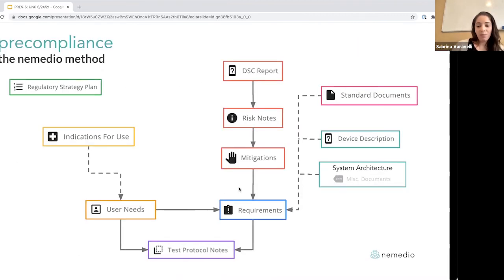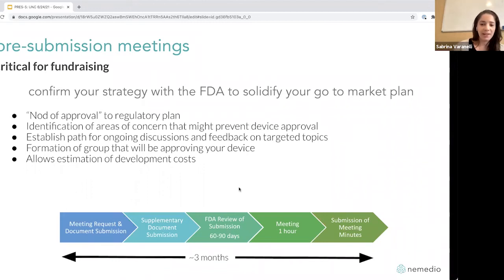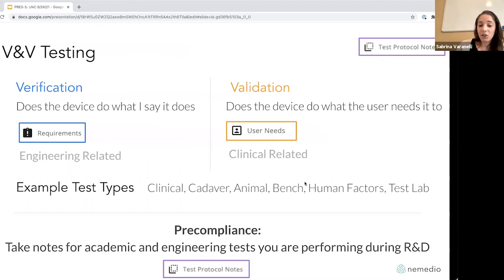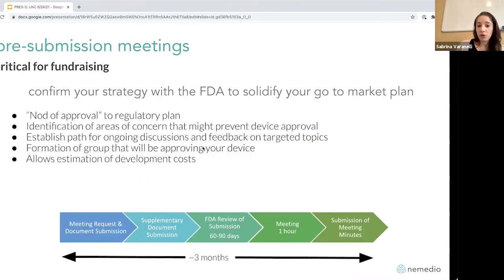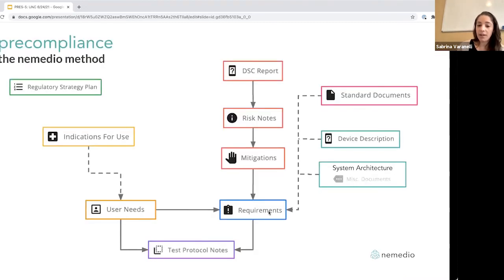Before I mentioned that the end result of all this work is a pre-submission meeting with the FDA. We at Nemedio very strongly recommend you meet with the FDA — it's not required, but some people avoid it because they think 'if we don't meet with them, they can't tell us to do stuff,' which is completely wrong. The idea is to confirm your strategy and testing plan with them — not only confirming your device classification and whether you're a 510k or DeNovo, but also getting FDA to look at your plan for clinical and engineering testing. You don't need a full protocol — having test protocol notes linked to your user needs and requirements is a good enough start for initiating the conversation.